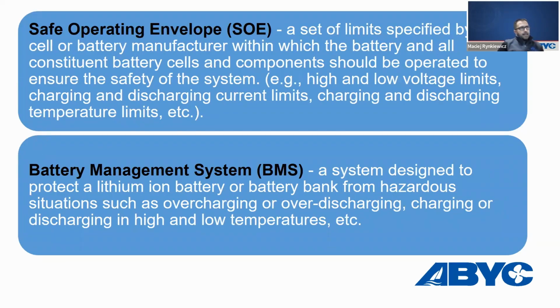So the other thing to remember is the safe operating envelope. That's a set of limits set by the battery manufacturer, for example high voltage limit, low voltage limit, high temperature limit, and low temperature limit, within which the battery is supposed to operate. If you go outside these limits, the battery management system will shut down, disconnecting the battery from the rest of the electrical system to protect the battery and the boat.